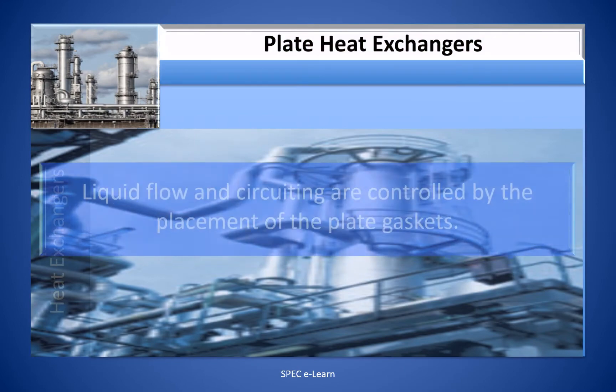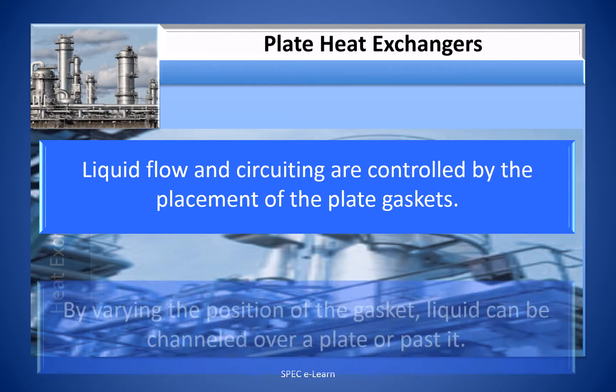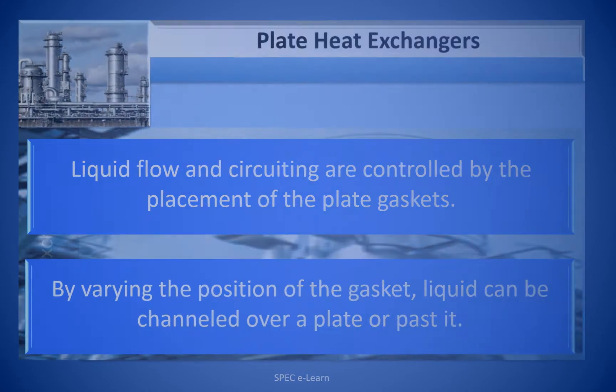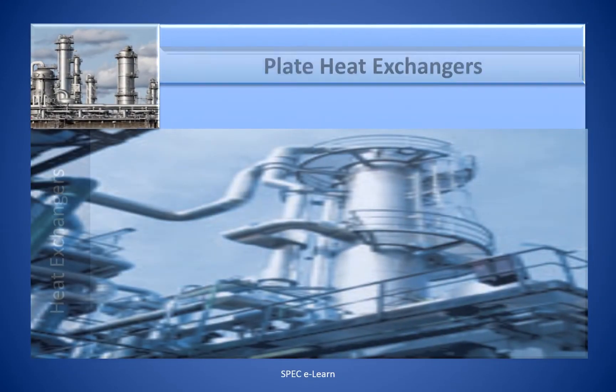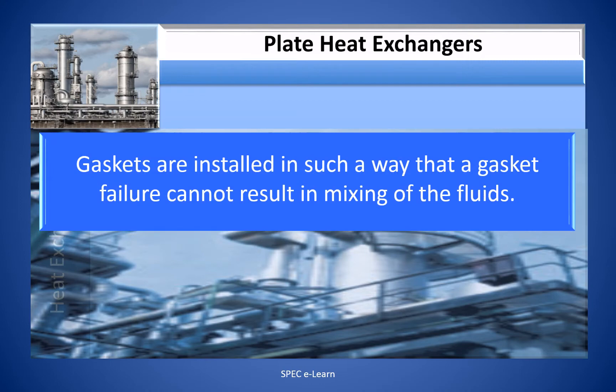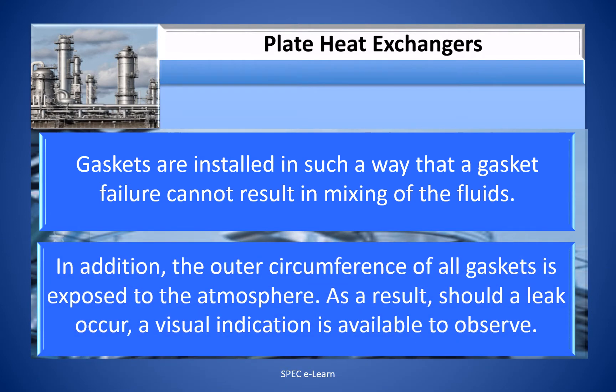The liquid flow and circuiting are controlled by the placement of the plate gaskets. By varying the position of the gasket, liquid can be channelled over a plate or bypassed. Gaskets are installed in such a way that a gasket failure cannot result in mixing of the fluids. In addition, the outer circumference of all gaskets is exposed to the atmosphere, so should a leak occur, a visual indication is available to observe.